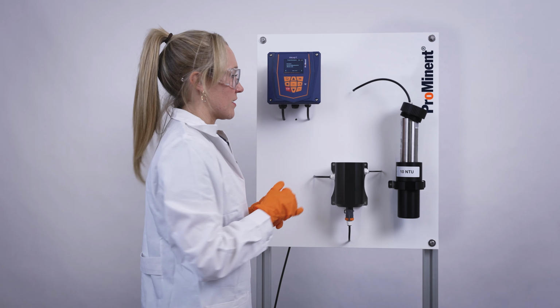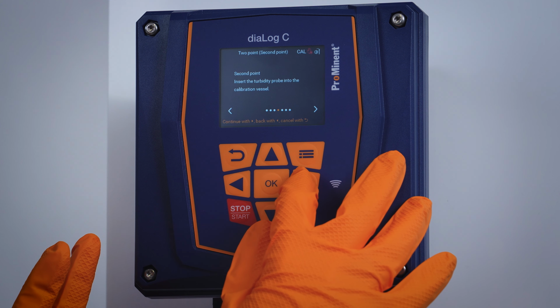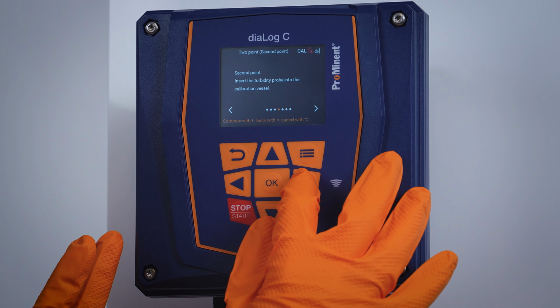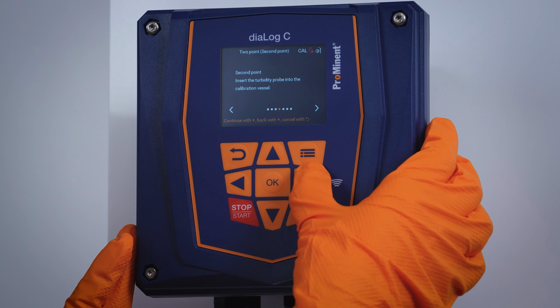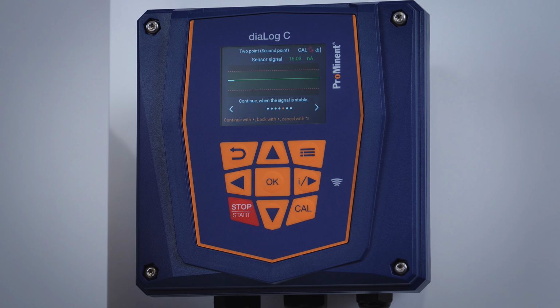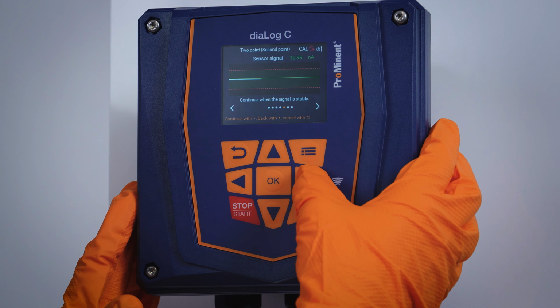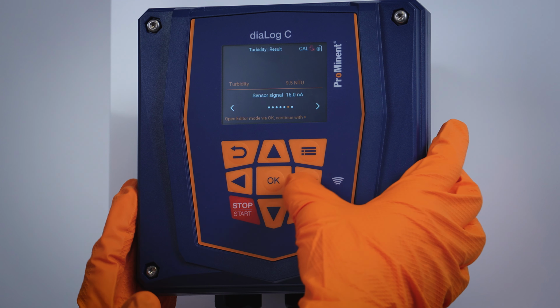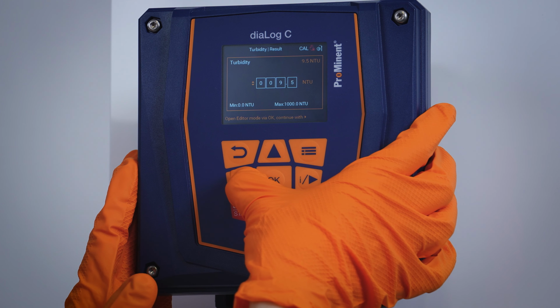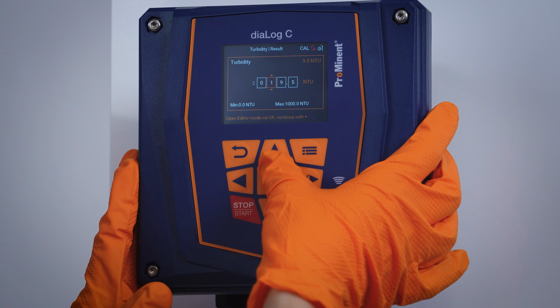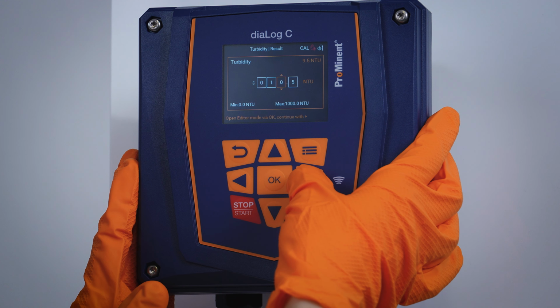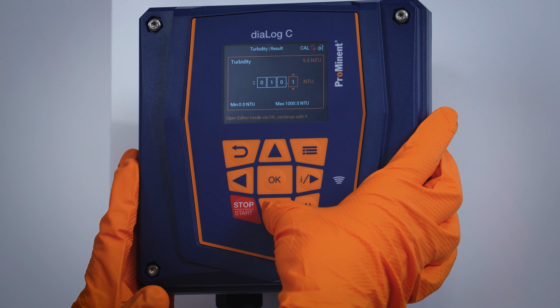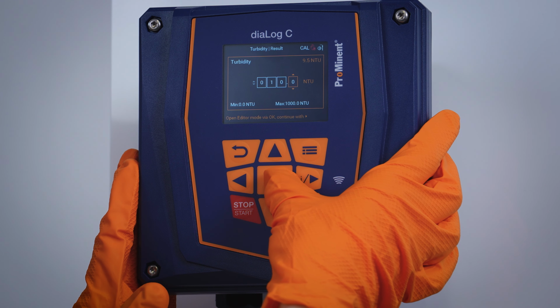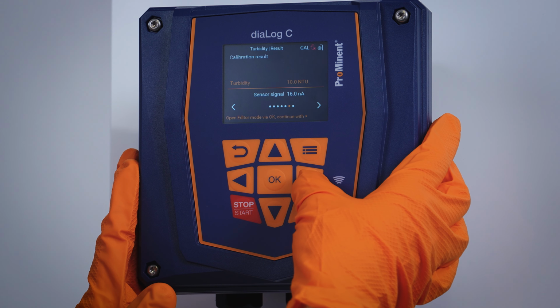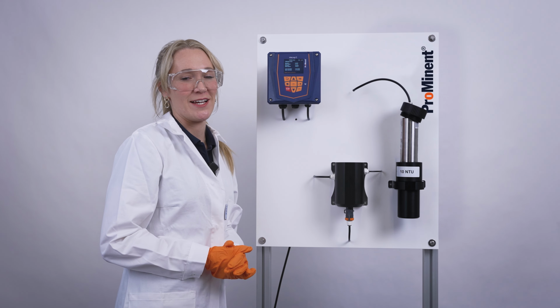Now, back on the controller side, you press next because you just inserted the sensor into the vessel. And now you wait again for a stable sensor signal. This looks pretty good, so we accept. And enter our value of 10 NTU. So that's it. Now our calibration was successful.